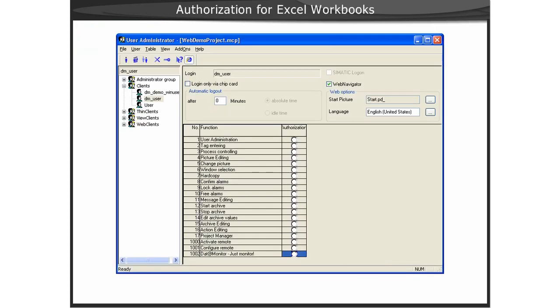When using Excel workbooks, whether the workbooks are being used locally or over the web remotely, a WinCC user must exist in order to access the online data. The user only needs to be added to WinCC. There are no special authorizations required for the user.